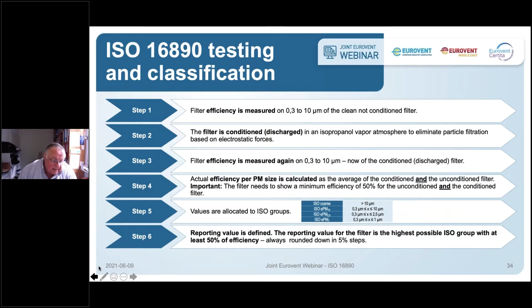That's an example of such a classification. So we have a filter that was measured in a new state and in a discharged state, and we are measuring on the same filter an ePM10 efficiency of 89%, an ePM2.5 efficiency of 63%, and an ePM1 efficiency of 49%. So that's the same filter, and it has different efficiencies according to these particle size classes. The minimum efficiency of 50% is achieved for the ISO ePM10 class and the ISO ePM2.5 class, because here we are over 50%. With 49%, the requirement for an ISO ePM1 is not fulfilled.